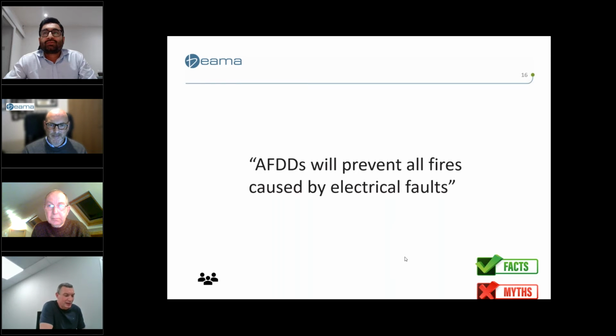AFDDs are primarily designed to detect and disconnect dangerous arcing faults that can't be detected by other types of electrical circuit protection devices. So they're definitely an important additional protection for the prevention of fires caused by electrical arcing faults. AFDDs are not the cure, not the be-all and end-all silver bullet — I don't think anything is. But they certainly provide a lot more protection than you can currently get from just a standard MCB, RCBO, or RCD type device. I think that's a key point, Ian.